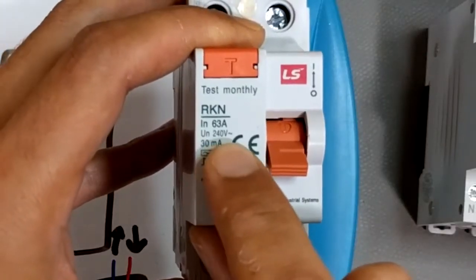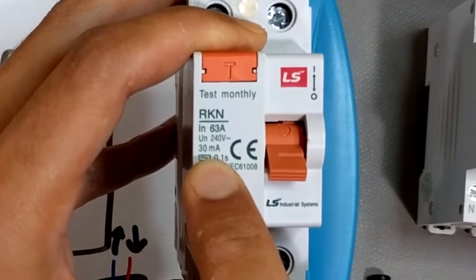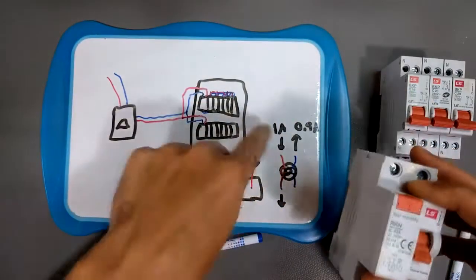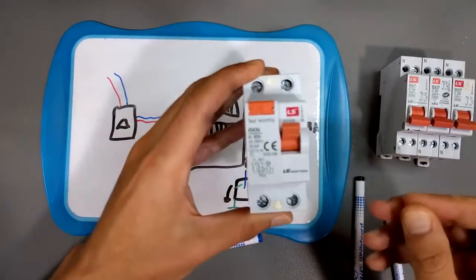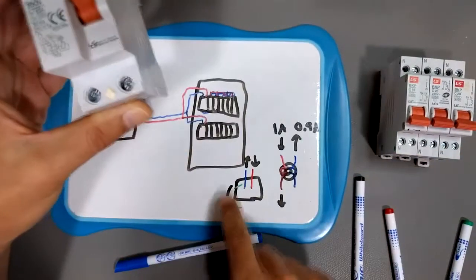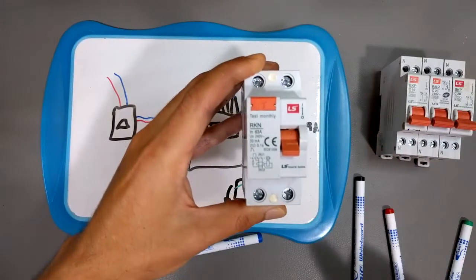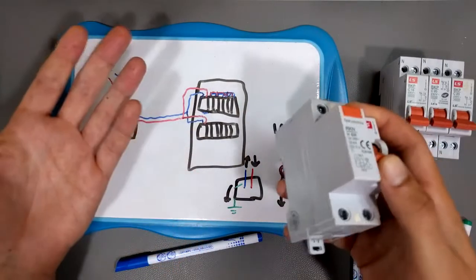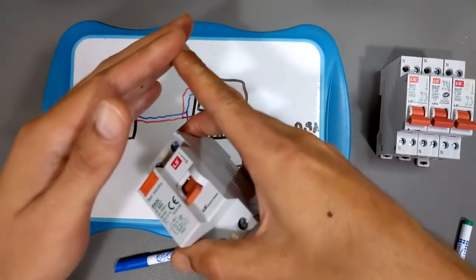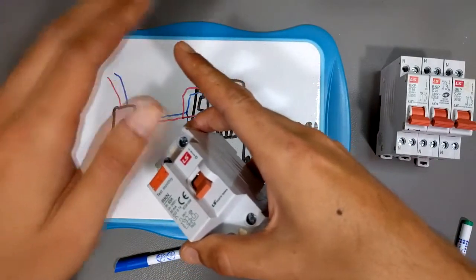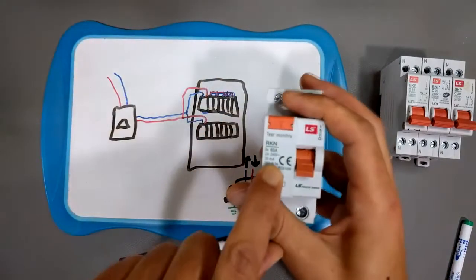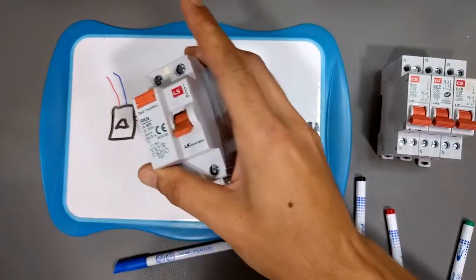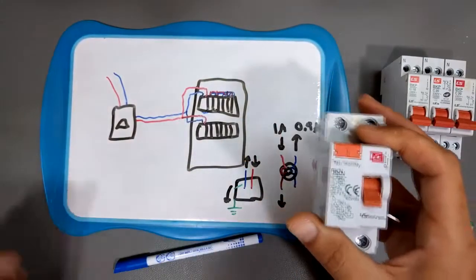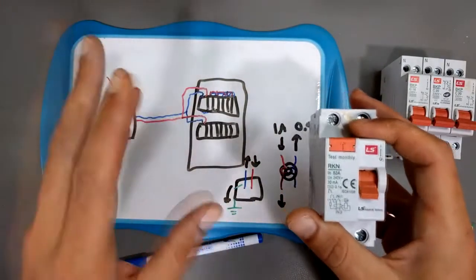It says your voltage is 240 volts, and 30 milliamps - that's the current differential this device will tolerate when it's on. When it detects 30 milliamps of leakage current or more, it trips. That protects against various device failures, and it's primarily for electrocution prevention, because if you touch a circuit or gizmo that's plugged in and there's a fault, when 30 milliamps or more of current starts flowing through you, this guy will trip. It's complicated why they picked 30 milliamps specifically.